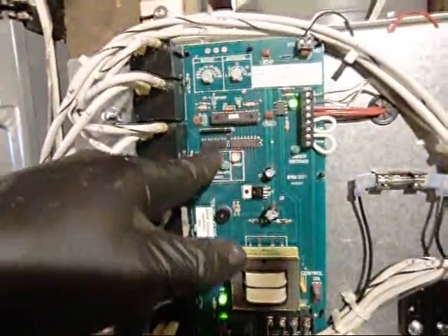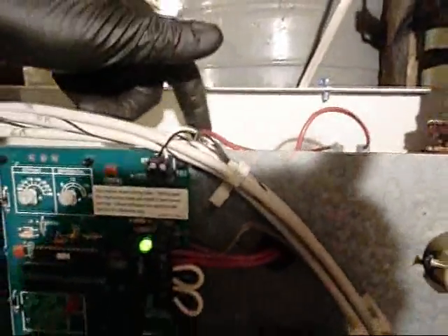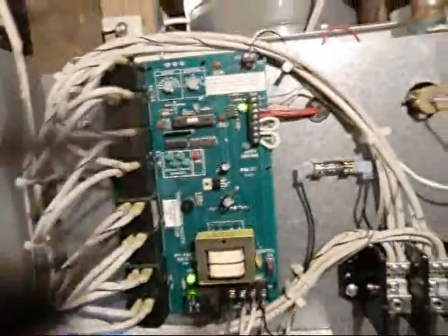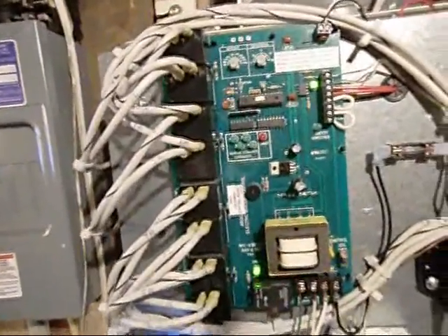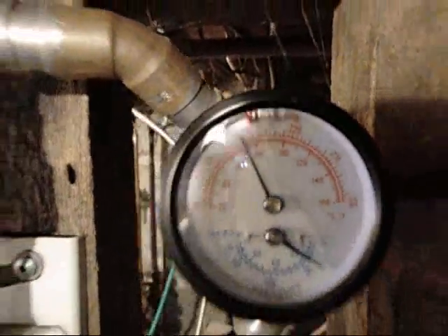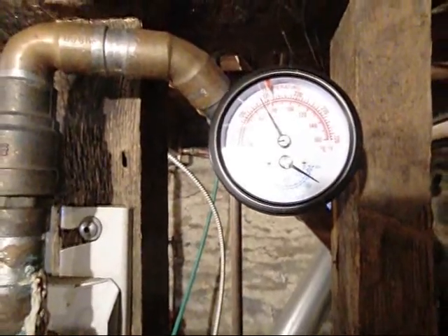The boiler was running all 4 elements. 1, 2, 3, 4. And one of the over limit switches, these are redundant, they both do the same thing, popped, opened, cut the power, and the computer said, that's not good, that's a fault. So, until the temperature goes down, and zone 2 is calling for heat. Thermostat's turned up, mercury touches the 2 wires together, circulation pump runs. So until this gets down below whatever temperature, we're down at 160 now, which is 72 Celsius.